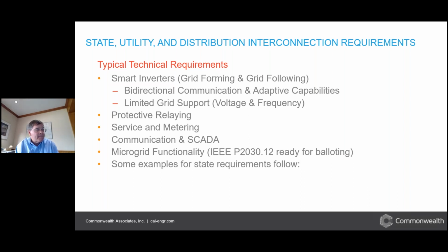Other areas, utilities are going to have their specifics. They may even say you will use this type of relaying. If you're wanting to connect to our system, you need to use these specific relays that we approve. Same with metering. They'll have requirements that need to be adhered to. Telemetry, communication, and SCADA. Specific polling requirements, depending on the size of the solar facility.